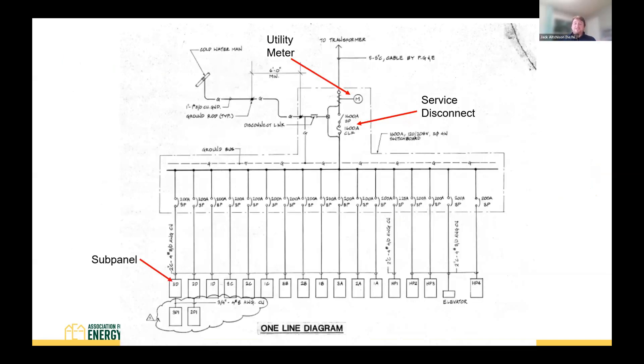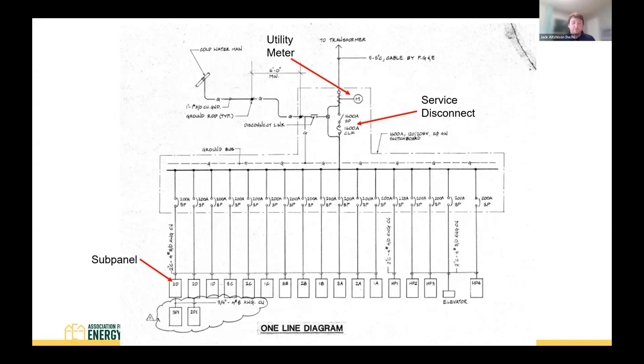The single line diagram from the actual building plans shows a setup more similar to single family: service coming in, then a meter, then a 1600 amp service disconnect, spreading out to individual sub panels. With 122 units at the site, there is not a sub panel for each dwelling unit — sub panels are located in the hallway and serve multiple dwelling units.